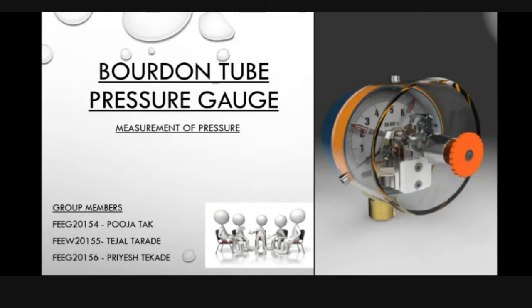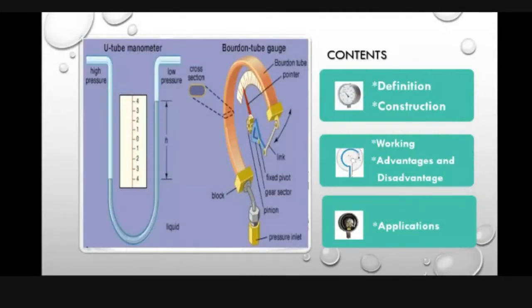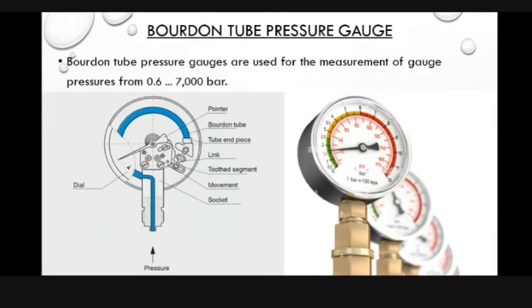We are going to give a presentation on the Bourdon tube pressure gauge. We are going to cover the following points in our presentation: definition, construction, working, advantages and disadvantages of the Bourdon tube pressure gauge, and application. Let's see what a Bourdon tube pressure gauge is. Bourdon tube pressure gauges are used for measurement of gauge pressure from 0.6 to 7000 bar. A Bourdon tube pressure gauge is a mechanical instrument that gives an accurate pressure measurement without requiring any electrical power.